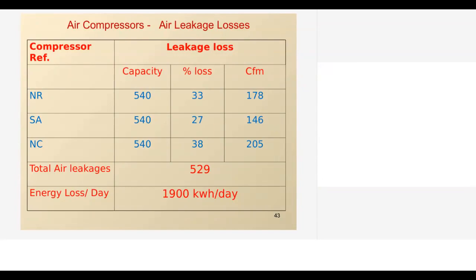Because sometimes people will ask, no, it is not possible. Everything is possible. Because of what we found in one large railway establishment we worked with: they are generating 3000 CFM, and the loss in the system is only 100 CFM. So now you can calculate the percentage. So never give any guideline for percentage. If they are able to reduce, they should reduce as much as possible.